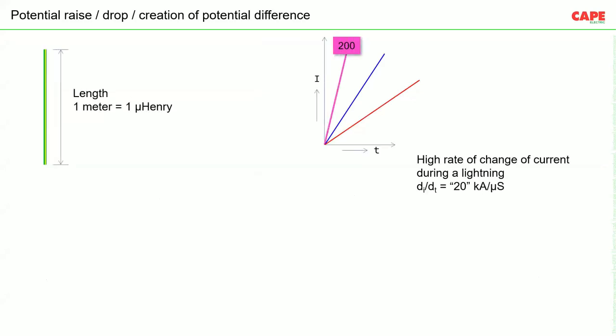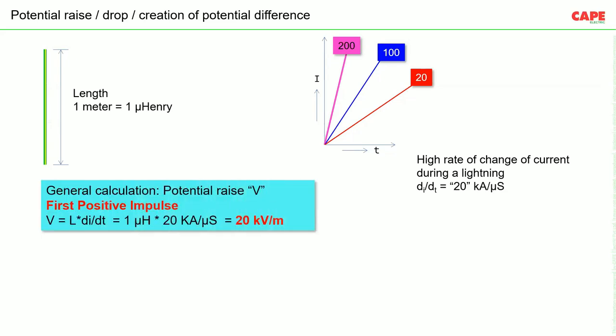Now, let us calculate how much the voltage drop will be in a 1 meter wire length. Generally, we know that a wire length of 1 meter will have an inductance of 1 microhenry. A general calculation for potential difference for first positive impulse, where di/dt was 20 kiloamperes per microsecond: V is equal to L di/dt. L is 1 microhenry and di/dt is 20 kA per microsecond. So there will be a potential drop of 20 kV per meter in case of first positive impulse, with a wire length of only 1 meter.